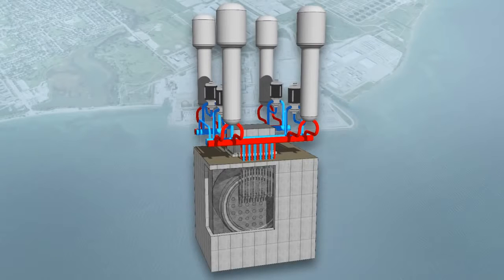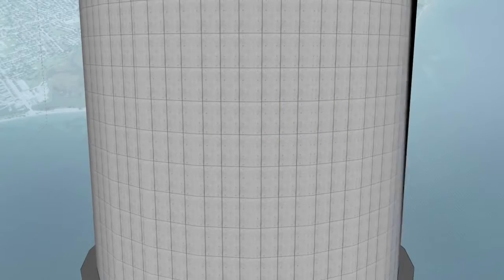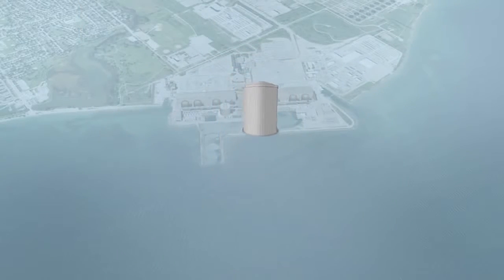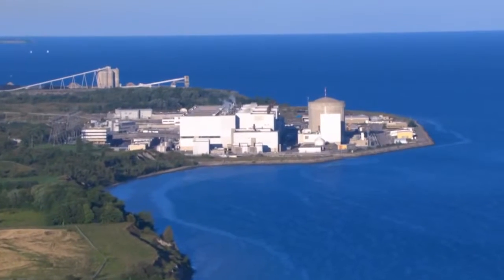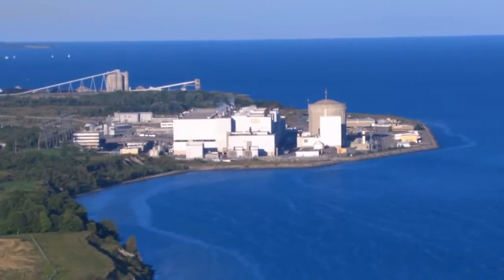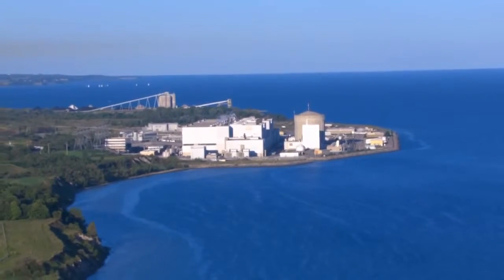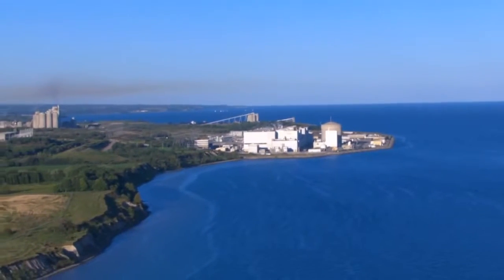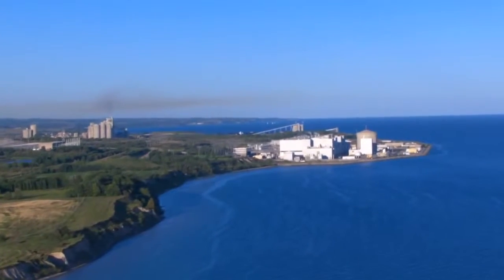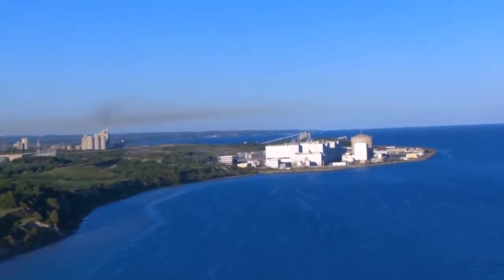The fourth layer of containment is the building that houses and protects the reactor. The walls of the reactor building are made of at least 1 meter of reinforced concrete. The reactor building is surrounded by a 1-kilometer exclusion or buffer zone. All plants are equipped with high-efficiency filters. These filters are used as part of the operation to minimize radioactive releases from nuclear power plants. These releases occur as part of normal activities like system maintenance. Filtering systems are regularly inspected, and power plant operators must, by law, report all radioactive releases into the environment.